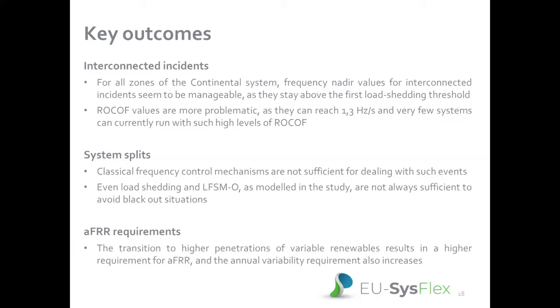For system splits, we observed that classical frequency control mechanisms were not sufficient, and even load shedding and LFSM-O, as modeled in the study, were not always sufficient to avoid blackout situations. Finally, the transition to higher penetration of VRES results in a higher requirement for AFRR, and the annual variability also increases. Thank you.